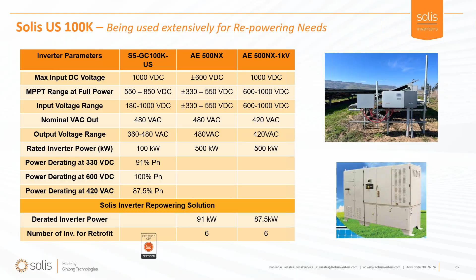This has made it a superstar in the repowering market. In many cases, you end up having to parallel together a number of these lower power strings, as shown in the top right corner of the slide. You see there's a combiner box being used with our 100K inverter, and because we've upped our game to 32 amps per input, not just per MPPT, but per input, we can really do some paralleling of these older, lower amp PV module strings in a combiner and bring it directly over to our inverter. So repowering for this line of inverters has been a really good seller for us.